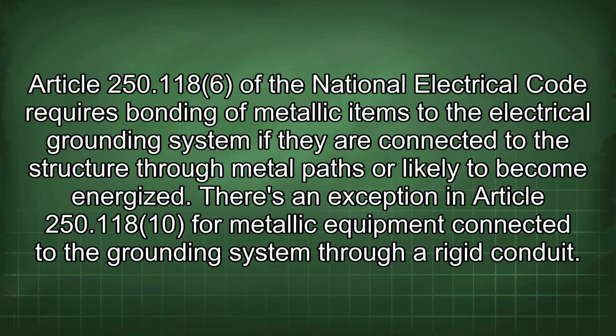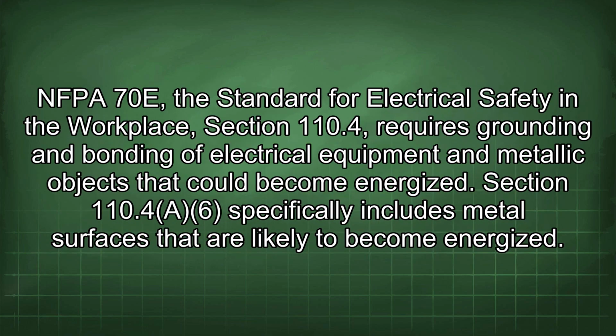There's an exception in Article 250.118 for metallic equipment connected to the grounding system through a rigid conduit. NFPA 70E, the Standard for Electrical Safety in the Workplace, Section 110.4, requires grounding and bonding of electrical equipment and metallic objects that could become energized. Section 110.4(A)(6) specifically includes metal surfaces that are likely to become energized.